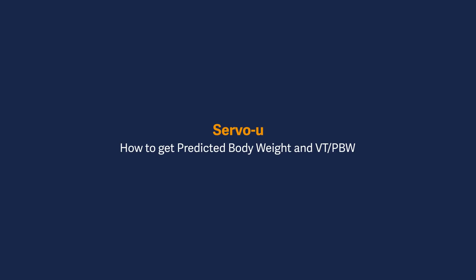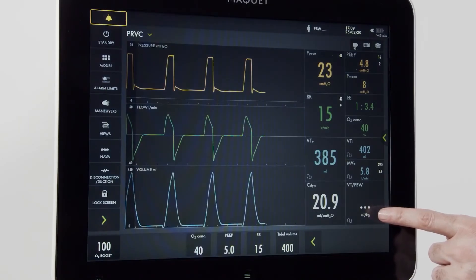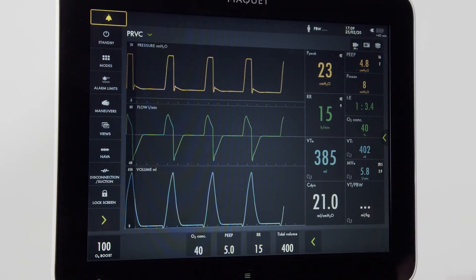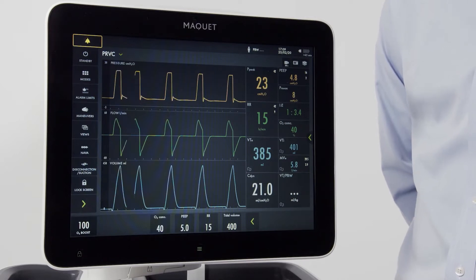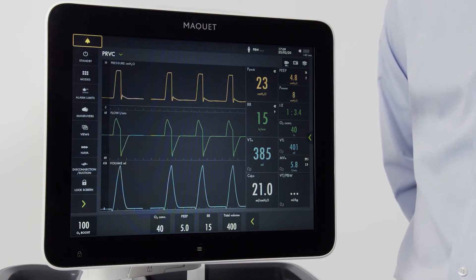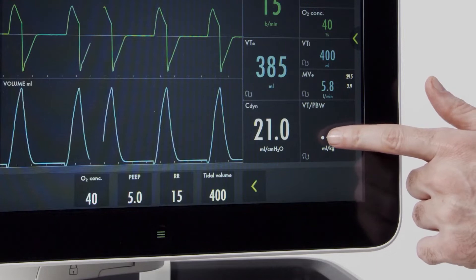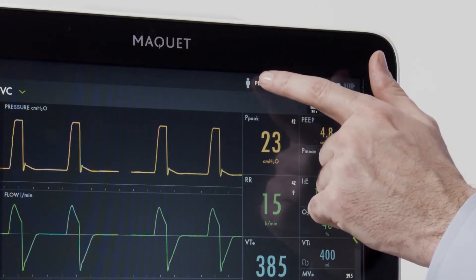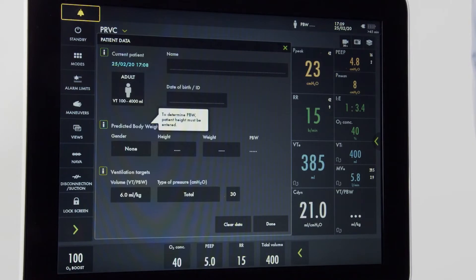Now that we're back to ventilation, note here in the corner that the volume per predicted body weight is not active. In order to get that information, we need to put some data into the ventilator. I could press the screen here, or I could go up to predicted body weight and press.